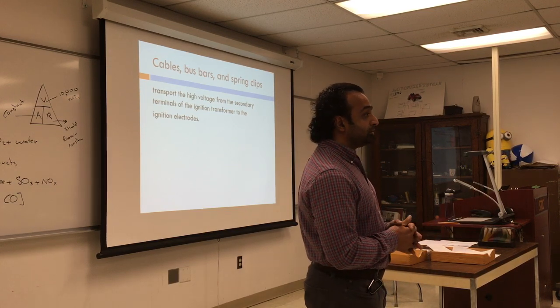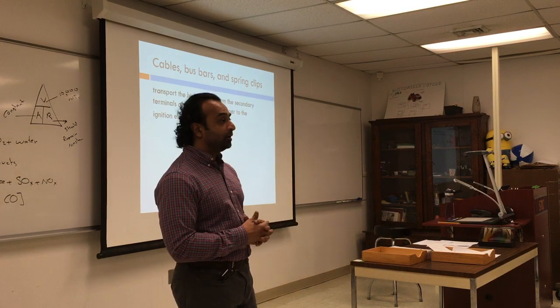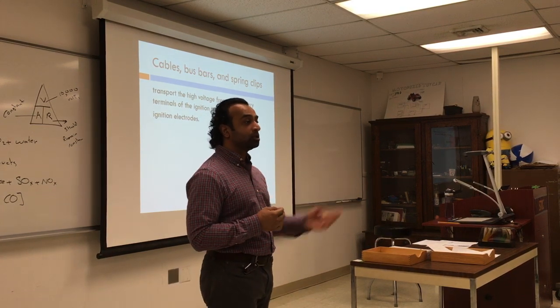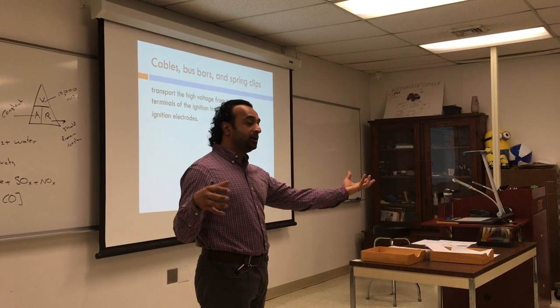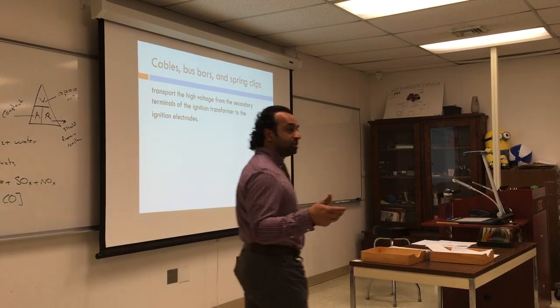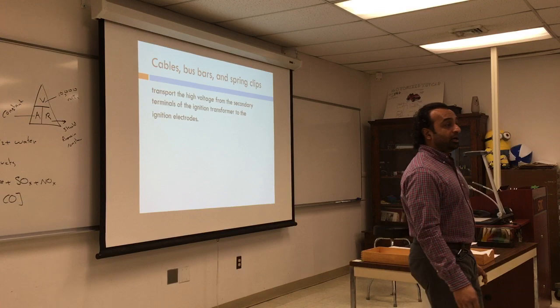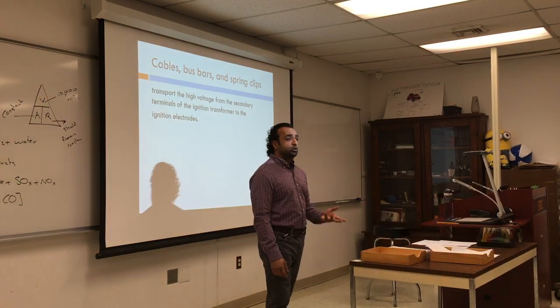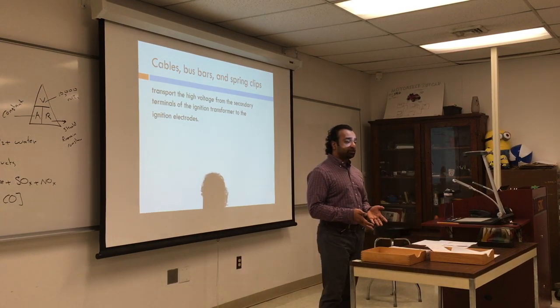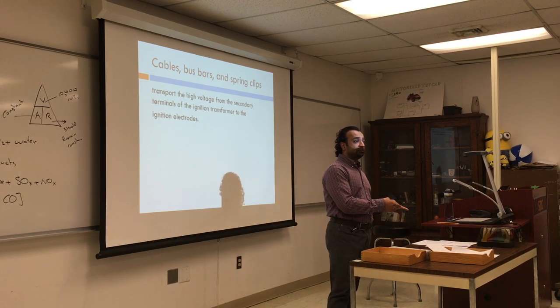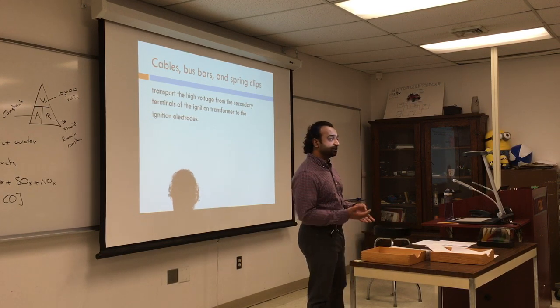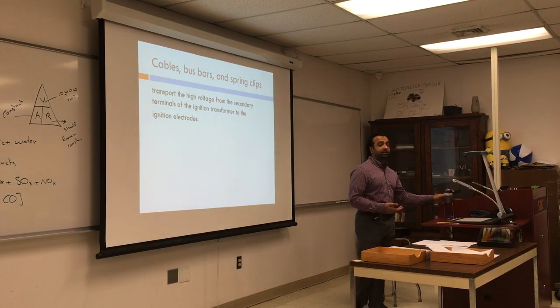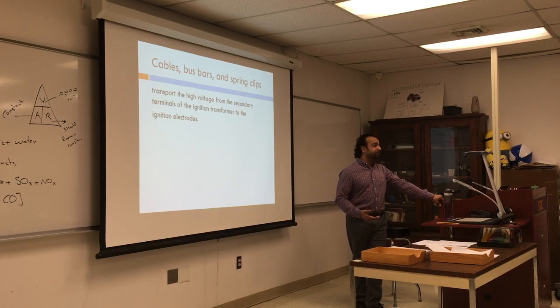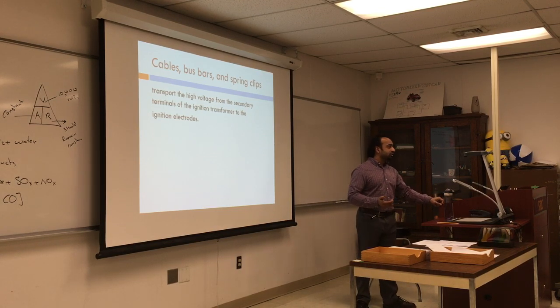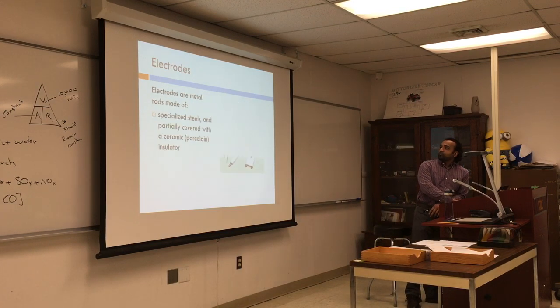If you go with industrial boilers, where you have very long electrodes and a long distance between the transformer and the electrodes, you might want to trace the voltage and make sure it's getting all the way there. There were so many cases where you're getting voltage coming out of the transformer, but you go to the electrodes and you don't find the same voltage. It's very frustrating trying to find where it's leaking, and there are ways to detect it, but be careful. You are trying to detect and trace voltage with 10,000 volts, so be careful when doing that.